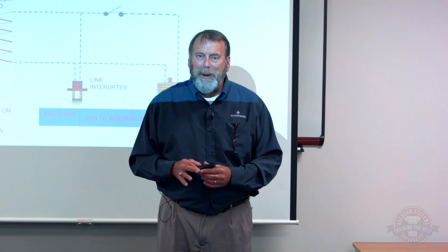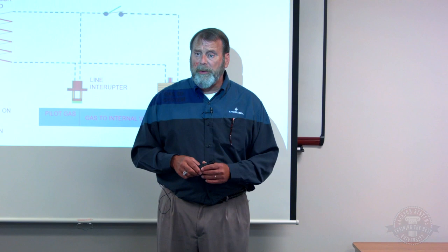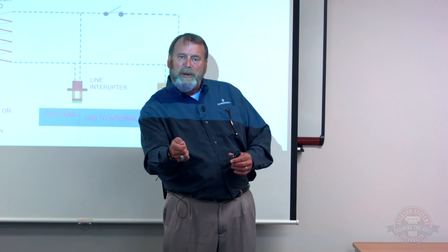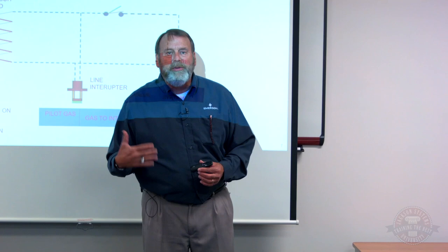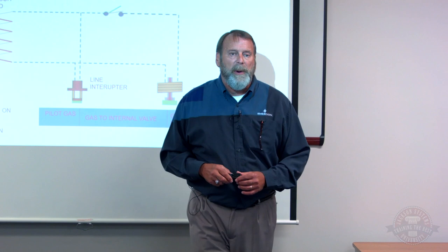What occurred was he had a 300 millivolt thermopile that he bought from the distributor. The gas valve was a 750 millivolt. So when he tapped it on the side, all he was doing was jarring things loose. It was not operating correctly. After going through some troubleshooting and checking the ranges like I did before, we were able to figure out he had the wrong voltage thermopile. So always ensure you know what you're replacing with the right millivolt thermopile. That's a little fun fact.